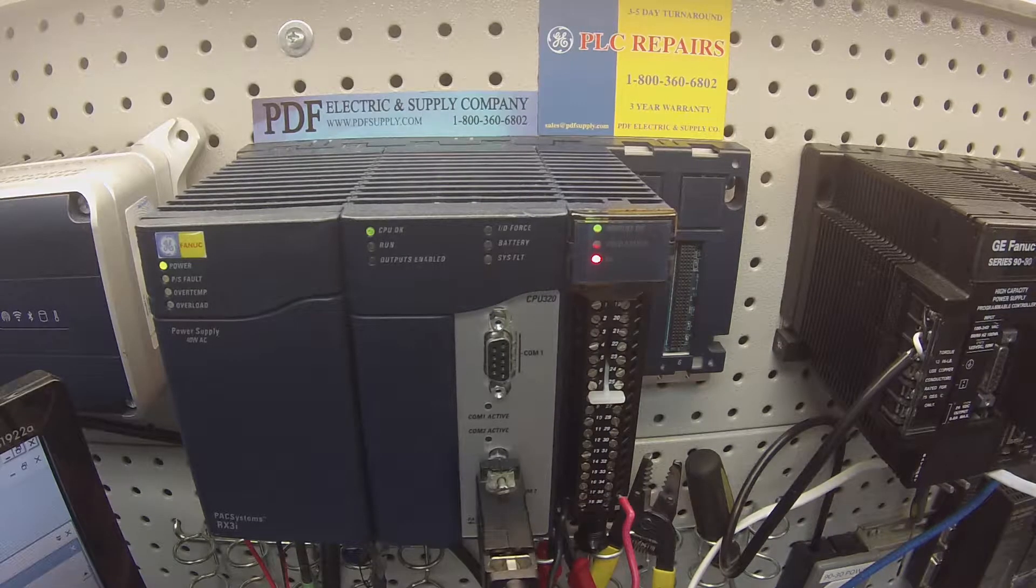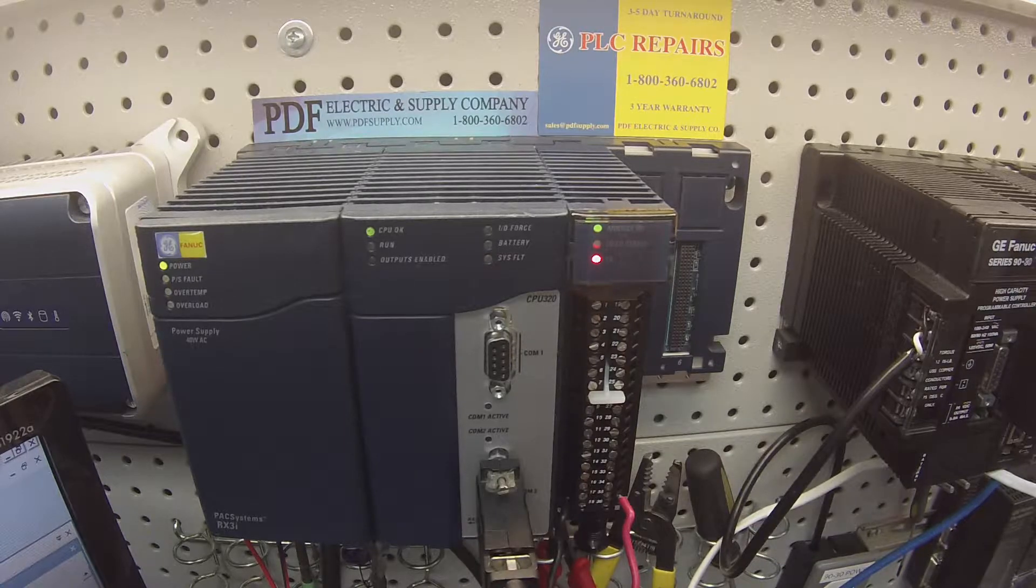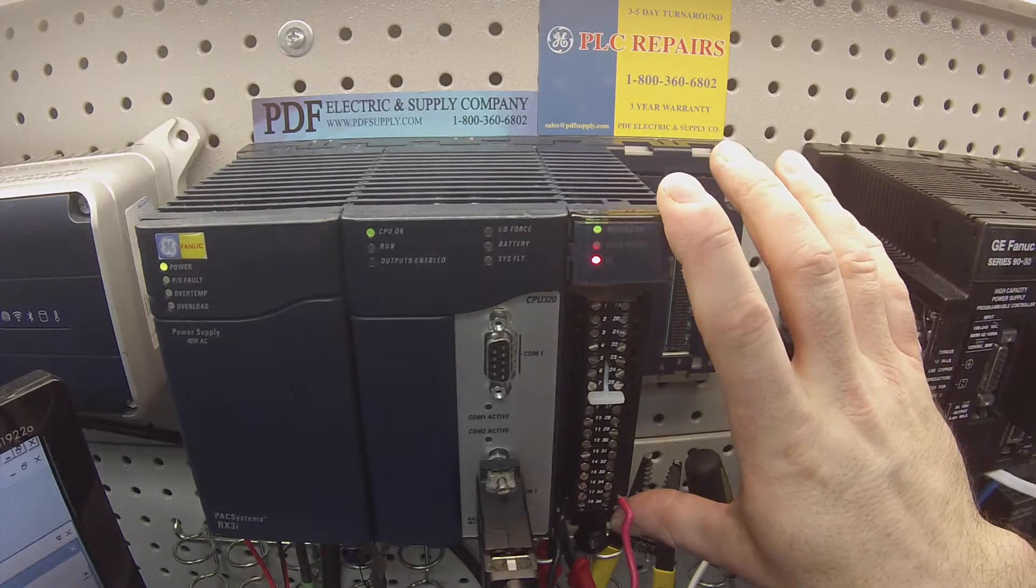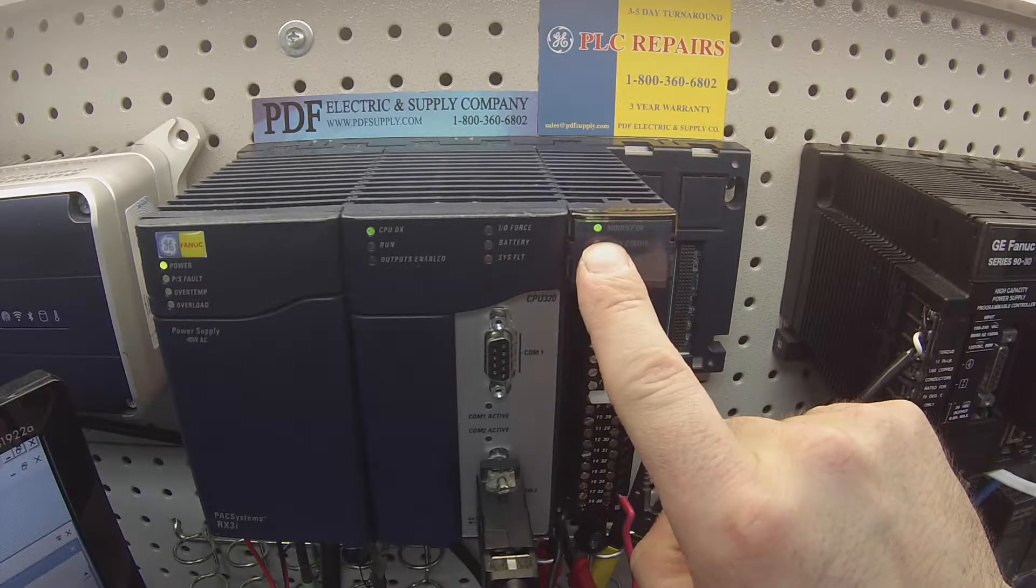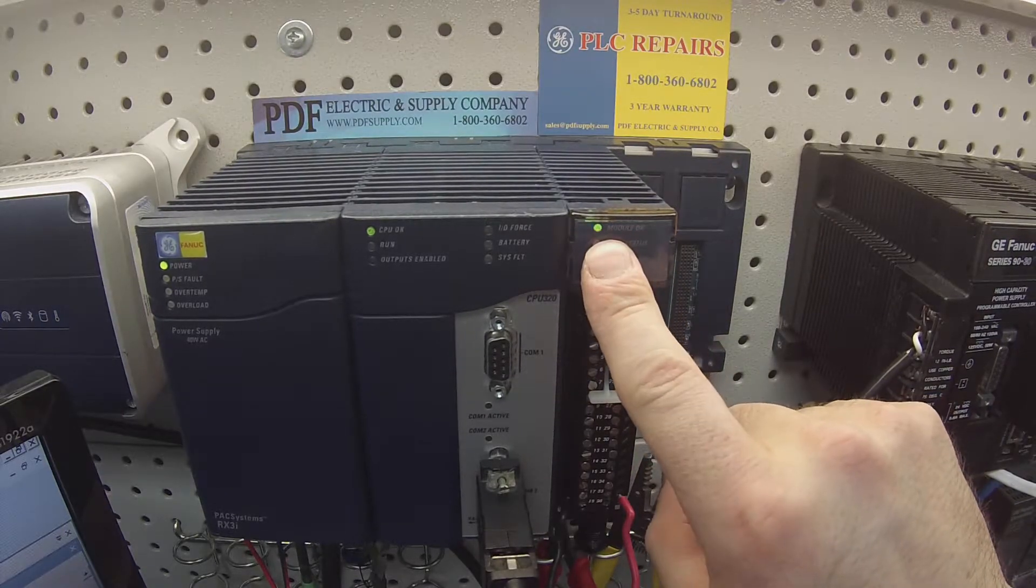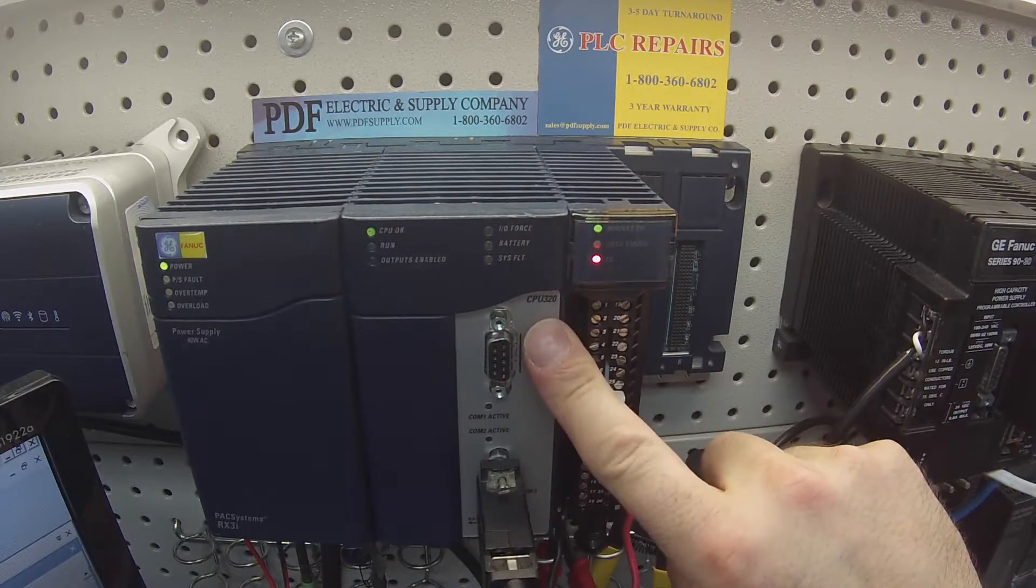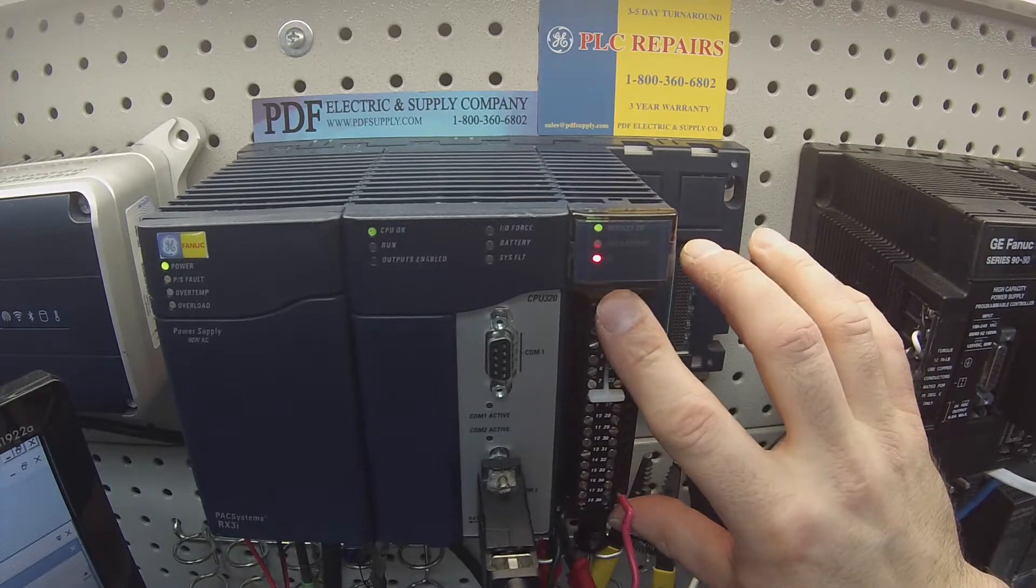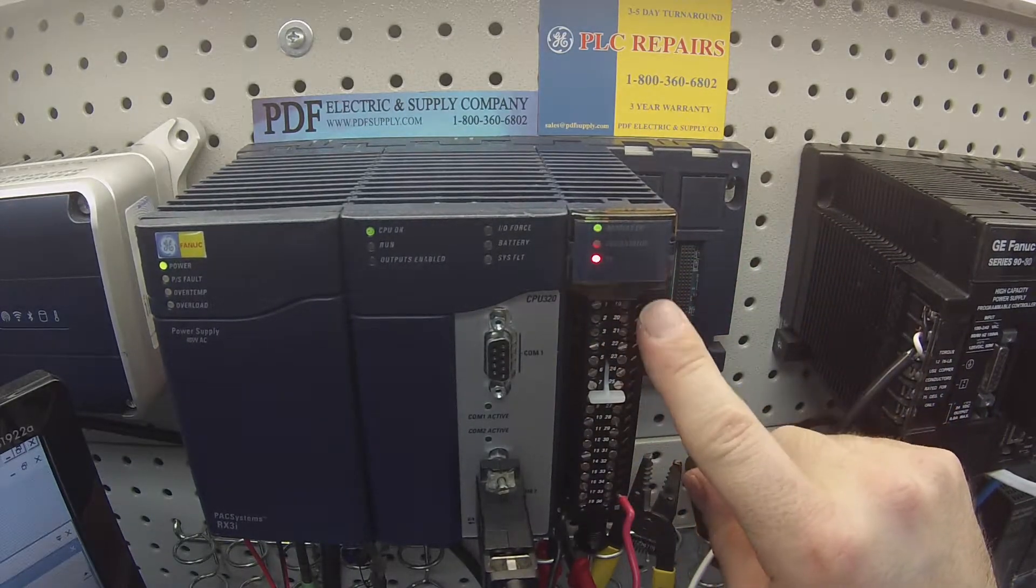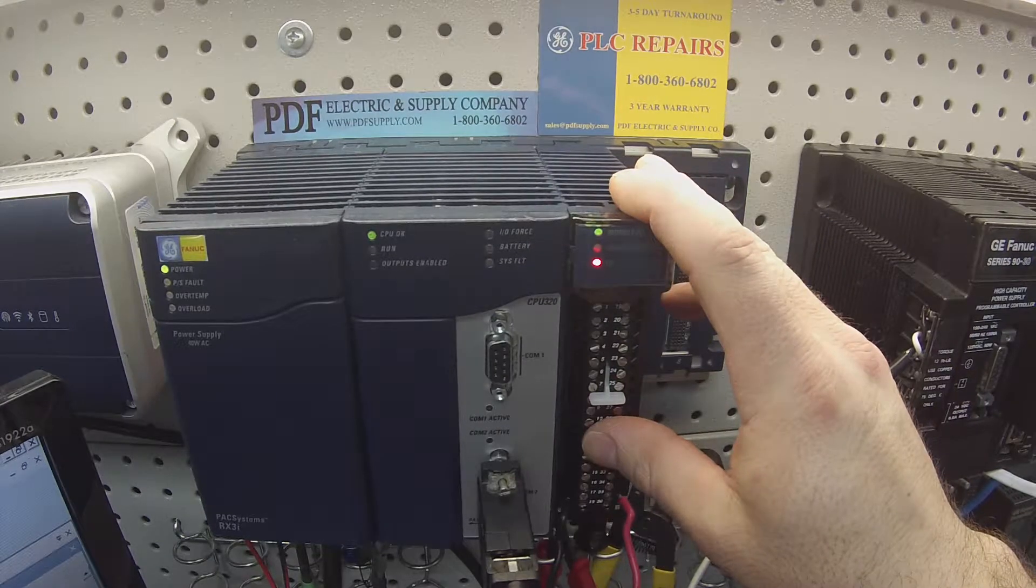It's four channels. A couple of things that I wanted to point out that you see in front of you first is the ALG module itself. Module OK light is blinking green. That's good. You need to make sure that you at least have a light on. If you don't have a light on when you plug it in and everything's powered up properly and it's secured to the chassis, then there's likely that there's an issue with the unit and it will need replacement or repair.